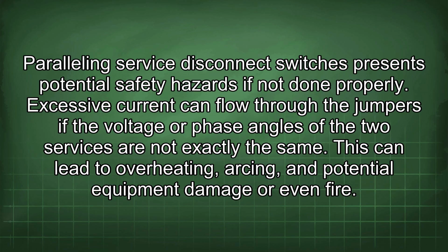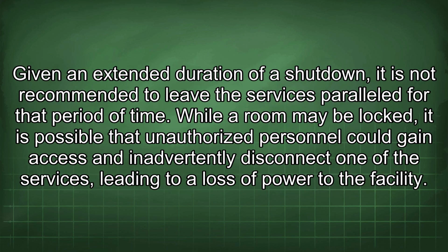Paralleling service disconnect switches presents potential safety hazards if not done properly. Excessive current can flow through the jumpers if the voltage or phase angles of the two services are not exactly the same. This can lead to overheating, arcing, and potential equipment damage or even fire. Given an extended duration of a shutdown, it is not recommended to leave the services parallel for that period of time. While a room may be locked, it is possible that unauthorized personnel could gain access and inadvertently disconnect one of the services, leading to a loss of power to the facility.